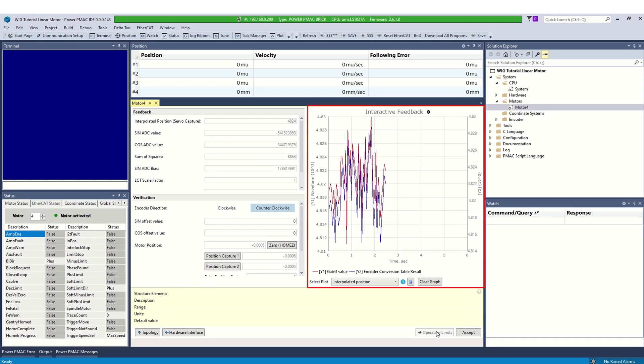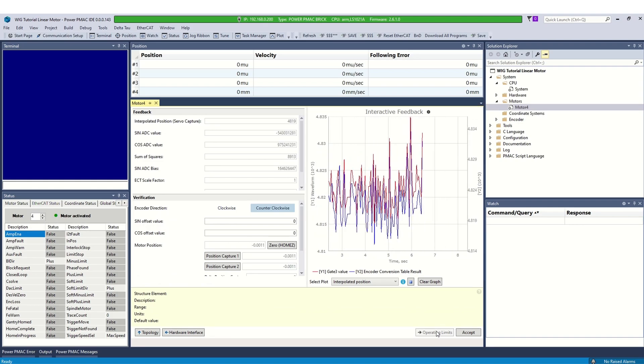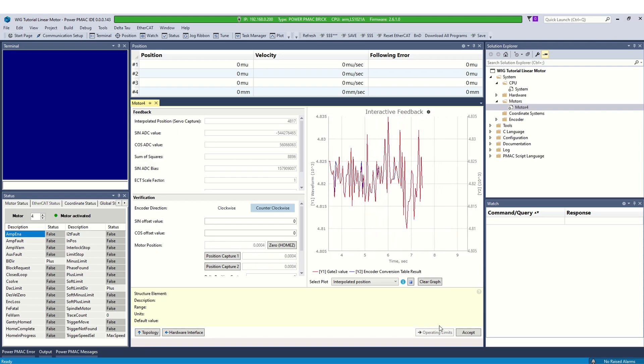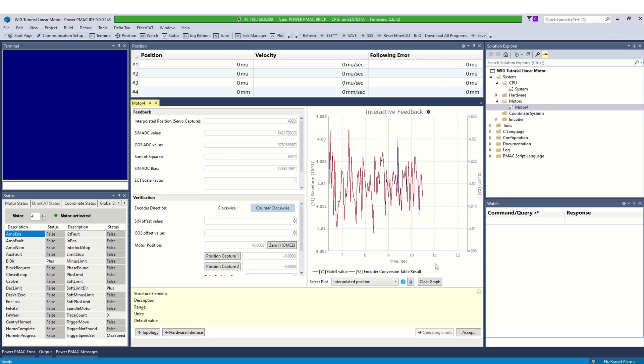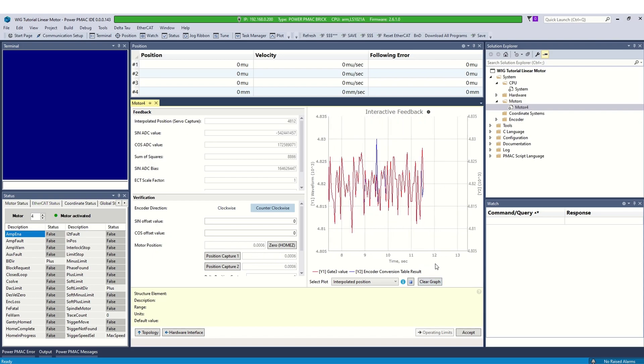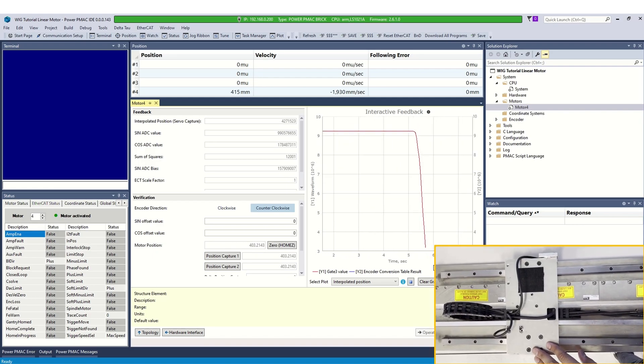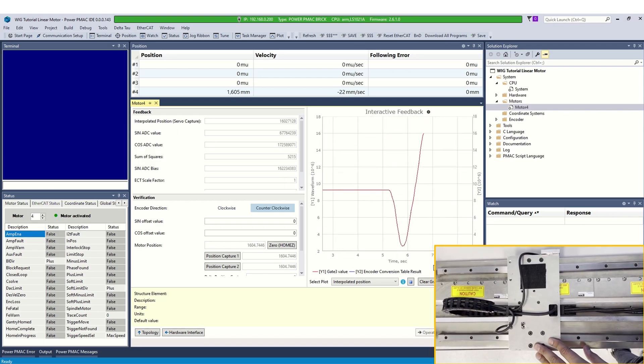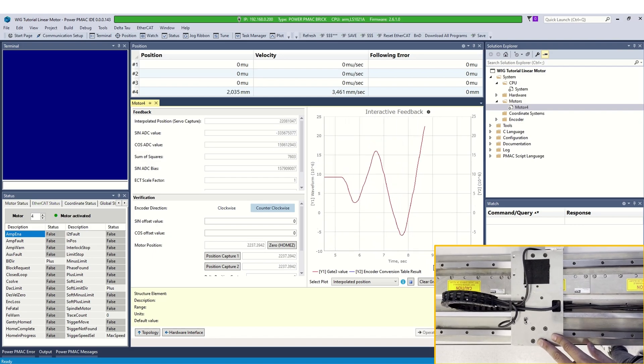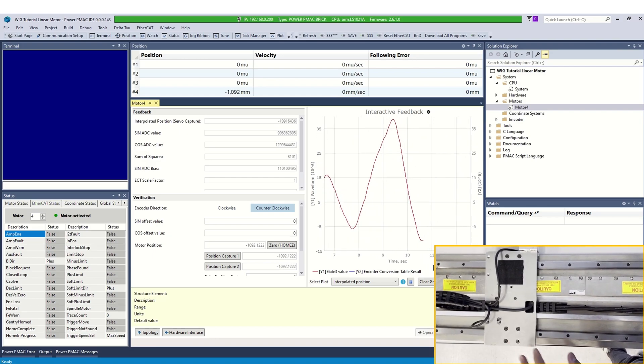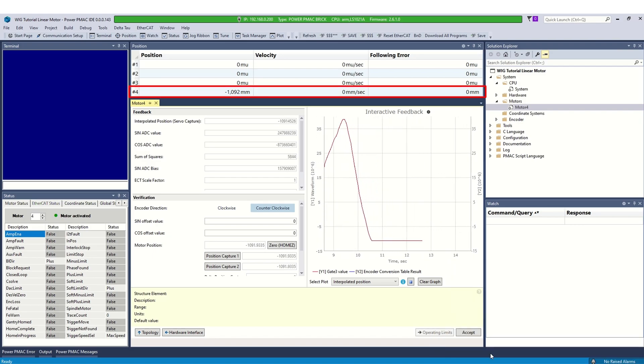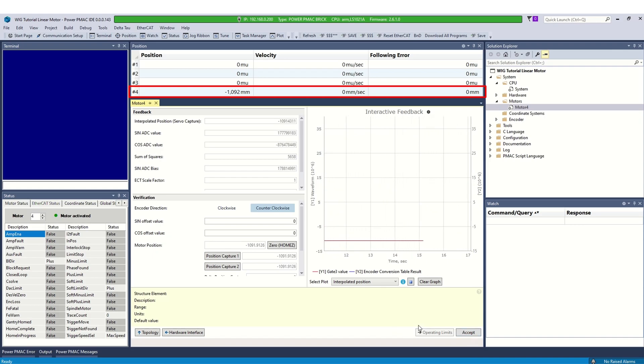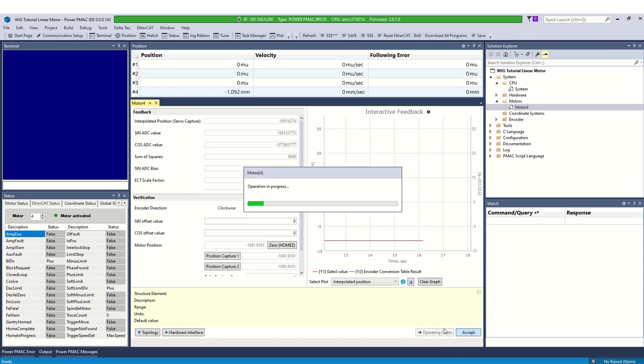Select accept to save and click on the interactive feedback. The interactive feedback screen displays real-time plot of feedback device. The purpose of this screen is to help determine whether the encoder feedback is working properly. Move the encoder by hand and observe the feedback on the screen. The plot shows the encoder position and the position at the top of the screen should change to indicate actual position. If you see the feedback, your encoder is working properly. However, if you do not see any feedback, you should look at the previous settings to make sure everything is set up correctly.